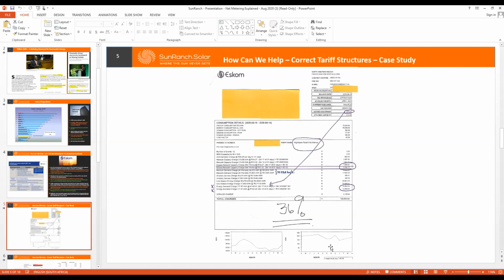But as you can see from the graph on the right-hand bottom, this client is using double the kVA of what he's got a connection point for. The only reason this system isn't blowing up is that the transformer is 350. But because Eskom has only allowed a 100 kVA draw point, and he's using around 200 to 250, he's paying massive penalties. When we went back through this account, we found the penalties originated around 2016, and his penalties for this excess usage amount to around 200% a year. When we advised the client of this, I think he was pretty horrified.